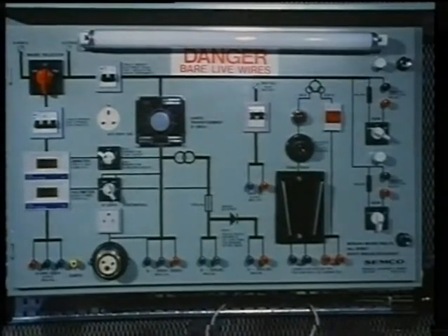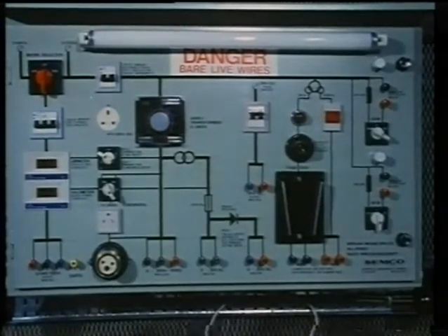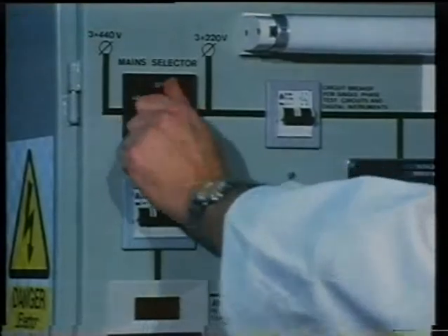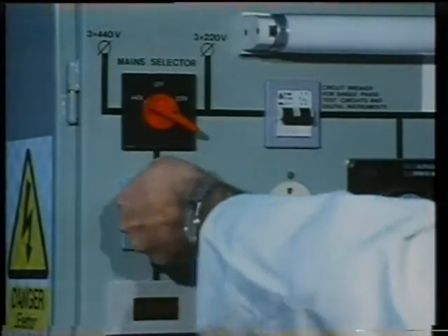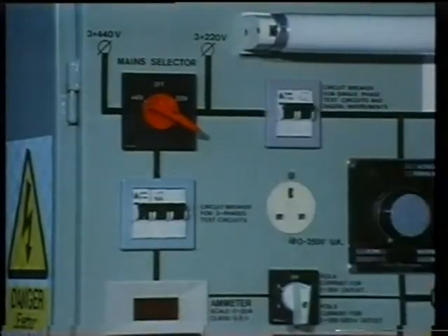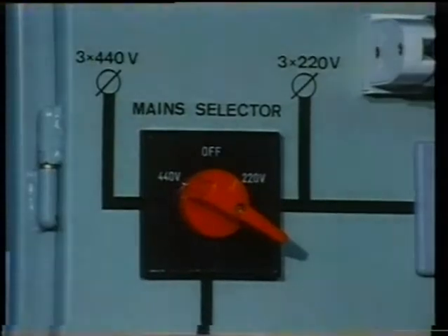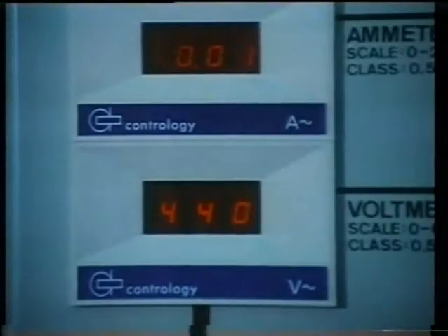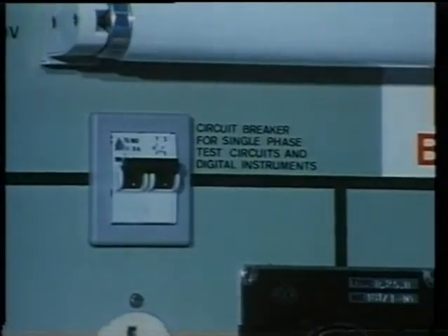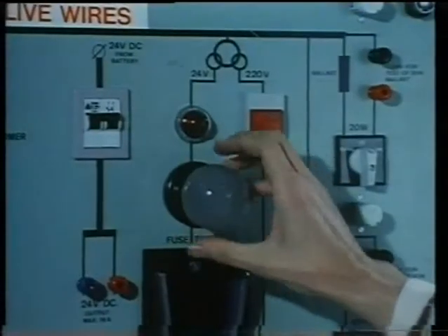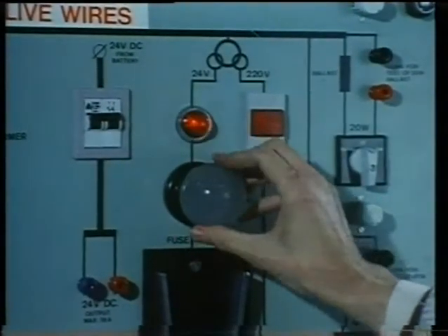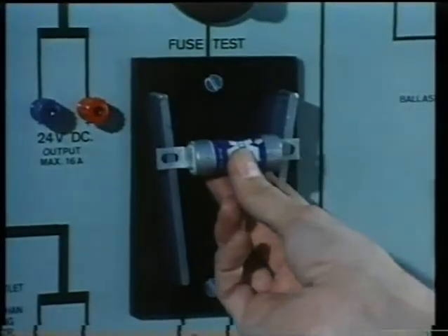Now let's look at some test instruments. The use of test instruments is a major element of electrical fault finding. They must be tested prior to their use to ensure complete reliability. For this purpose, a known supply of electricity is available at the electrician's test panel. Most test panels also provide testing for lamps and fuses.